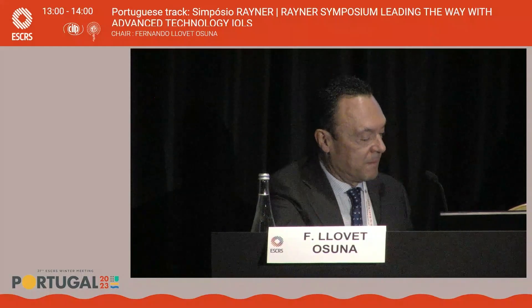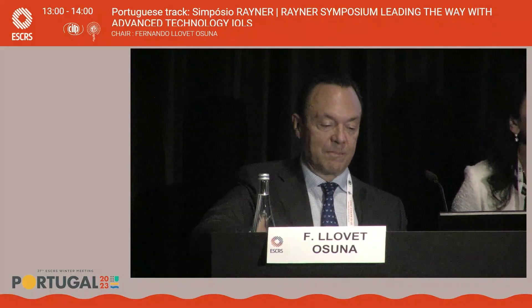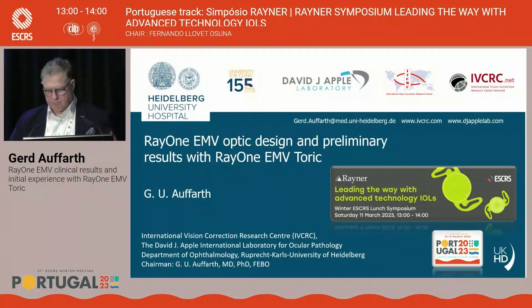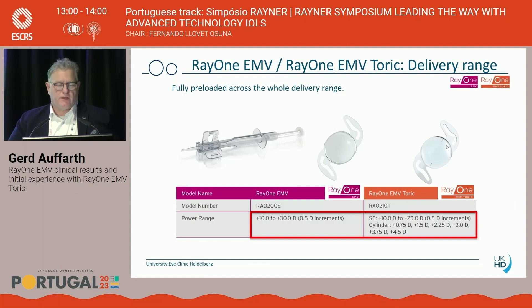Professor Auffarth. Thank you very much, and thank you also to Rayner for organizing this nice symposium. I will now talk about the EMV optic design and first results also with the toric lens. The RayOne EMV monofocal and EMV toric can be delivered with this very nice injector. The power range goes up to 30 diopters and the cylinder is available in 0.75 diopter increments, going up to 4.5 diopters.